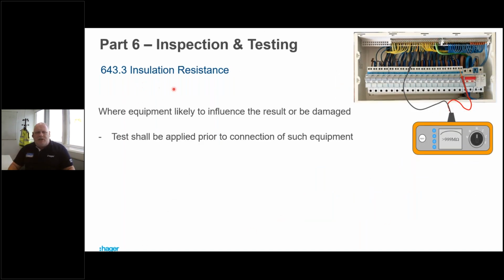Inspection and testing. 643.3, insulation resistance. And we say here, where equipment likely to influence the result or be damaged, the test shall be applied prior to connection of such equipment. What equipment are we talking about? We're talking about LED drivers. We're talking about USB sockets. These can have a detrimental effect on our results.